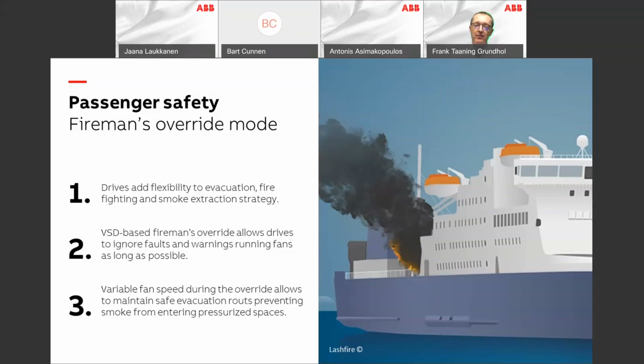With the drives, we have a fireman's override function that actually secures that no matter what happens, the drive will prioritize running the fan before protecting itself. Under normal operation, if the ambient becomes too hot, the drive might reduce the speed of the fan. It might even shut down entirely, simply to avoid a component failure. But in a fire situation, it's life and death. And then the equipment can be set with a simple switch or the signal from a controls that you have to prioritize the operation over the protection of the components.